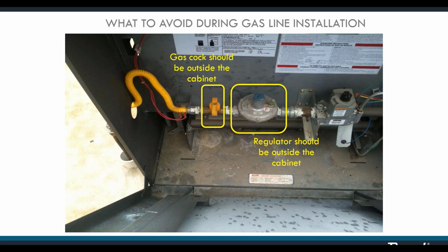NFGC does require one of those, but it's supposed to be within 6 feet of the heater, but it should be, again, on the outside where it can be easily found by anyone who might be looking for that sort of thing. The use of a flexible gas line is also not recommended. They are restrictive, they are noisy, and the right size is rarely used. Most people just use a 3/4 inch, and that very likely is not going to be big enough to accommodate the rate of flow, to accommodate the volume that you would need.